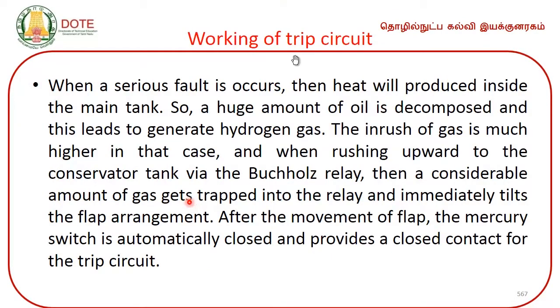Now, let us move on to the working of trip circuit. When a serious fault occurs, then heat will be produced inside the main tank. So, a huge amount of oil is decomposed, and this leads to generate hydrogen gas. The inrush of gas is much higher in that case, and when rushing upward to the conservator tank via the Buchholz relay, a considerable amount of gas gets trapped in the relay and immediately tilts the flap arrangement. After the movement of the flap, the mercury switch is automatically closed and provides a closed contact for the trip circuit.